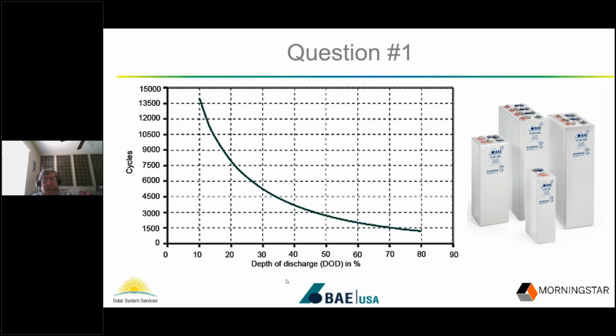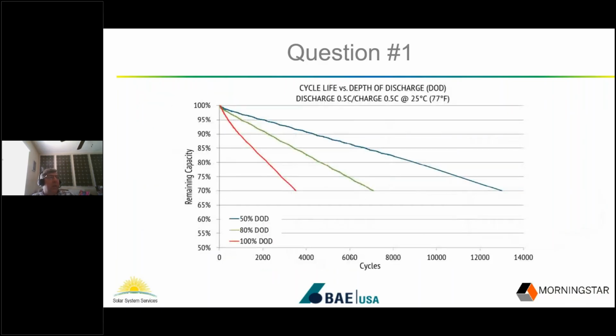I also want to point out that lithium batteries have the same problem. As you can see here, this is a lithium battery where at 50% discharge, they're getting around 13,000 cycles. They're only getting 7,000 at 80% discharge, and they say it can discharge to 100% getting around 3,500 cycles. But again, I question that, because at 100%, I don't think your load's going to function anymore. So what I'm trying to say is that cycle life versus discharge applies to all batteries, not just lead acids, by the way.